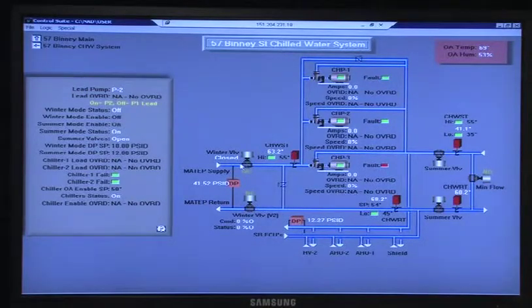So if your chiller is enabled and it goes below 50 outside, it's going to shut the chiller off. I'm sorry, if it goes above 50, it's going to enable. If it goes below 50, it's going to shut the chiller off. We're starting to get to these nights that it's getting cooler out. So, I'm just going to recap what Frank just said.